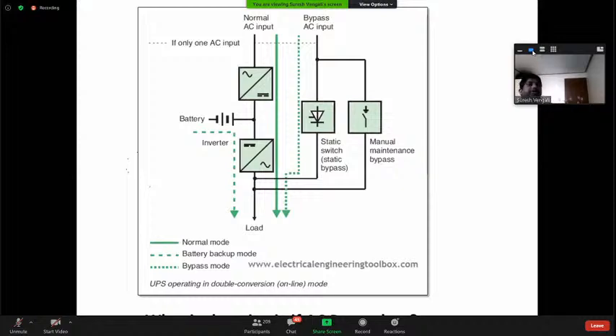So how do you maintain it in normal life condition? In a power plant, normally you may not lose any power, and even if you lose normal power, you have a bypass source, and after that your battery comes in. That means your battery is in an idle position even while the power plant is operating, so there are chances of self-discharge. To maintain the charge, you need to feed a little load here and the remaining load there.